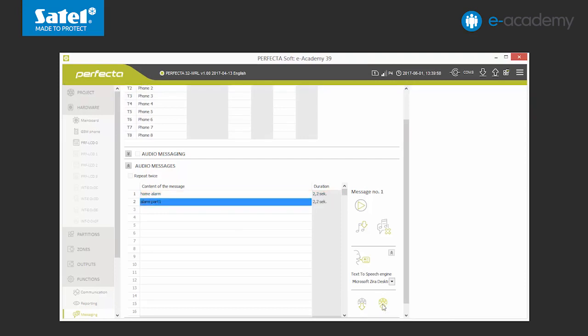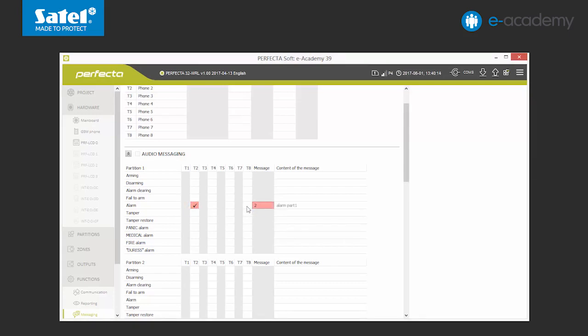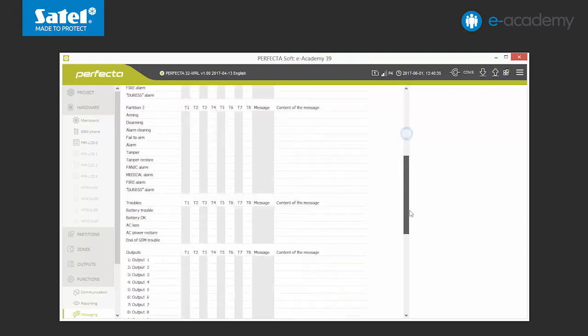Next, we can move on to select the events of which the system should notify us by audio messages. At each event, for example, an alarm in the first partition, we mark which phone should be informed and we specify the message number. Finally, we turn the audio notification services on and send the data to the control panel. In case of an alarm, the set control panel will call the specified number and play the relevant message.